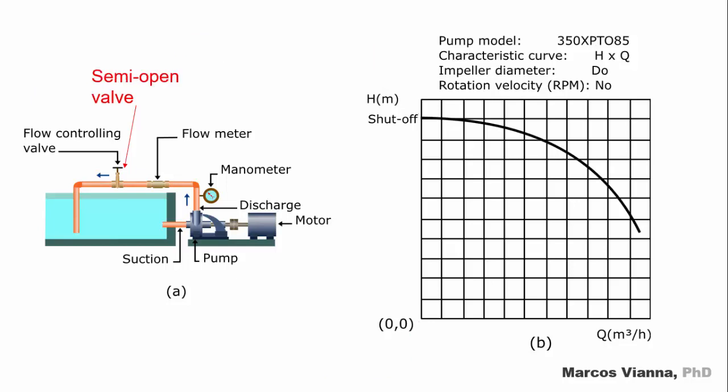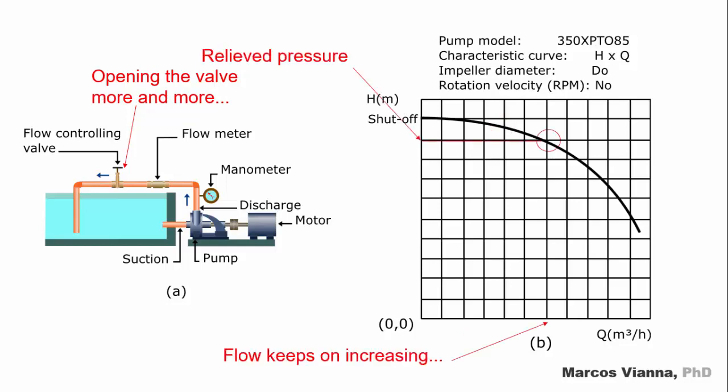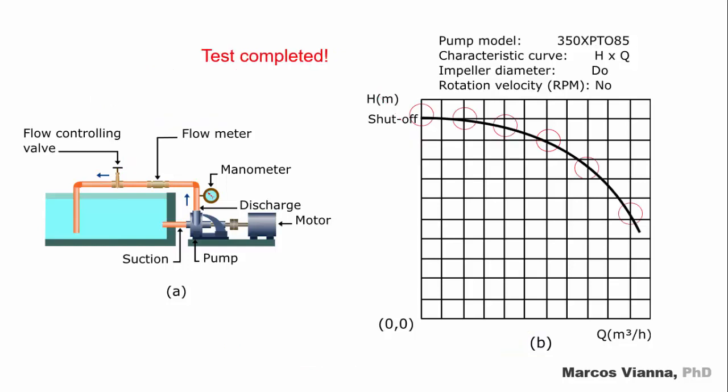Now we open the valve a little. Some flow will be allowed in the system and some relief at the discharge of the pump will be noticed. Now we open the valve a little more. The flow in the system increases and more relief at the discharge of the pump will be noticed. And we keep on doing this. Open the valve a little more. The flow in the system increases and more relief at the discharge of the pump will be noticed.